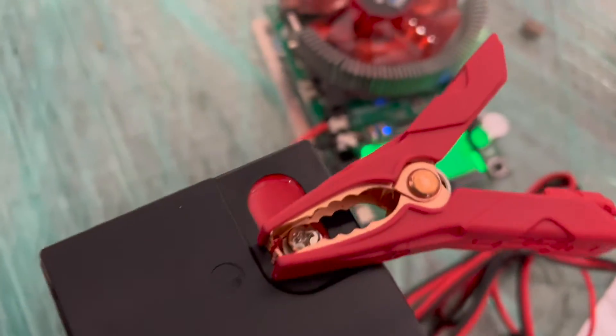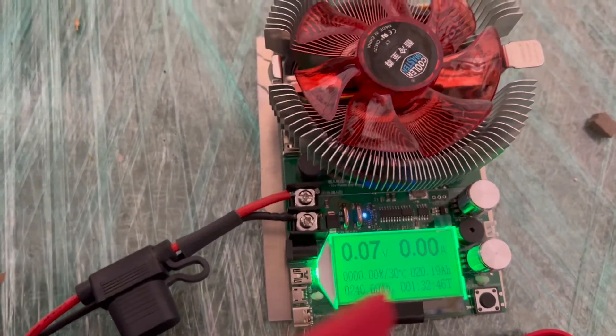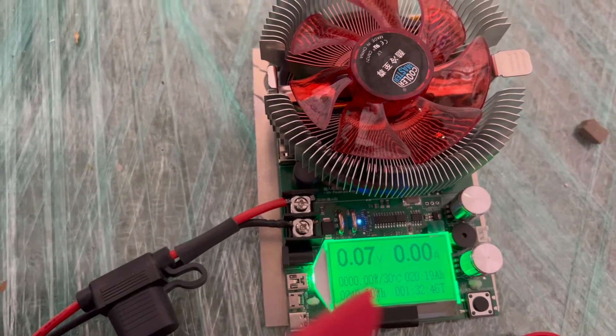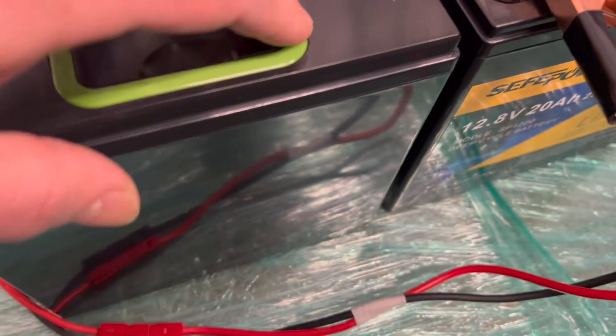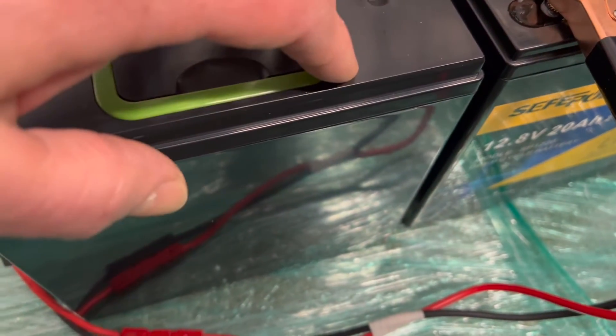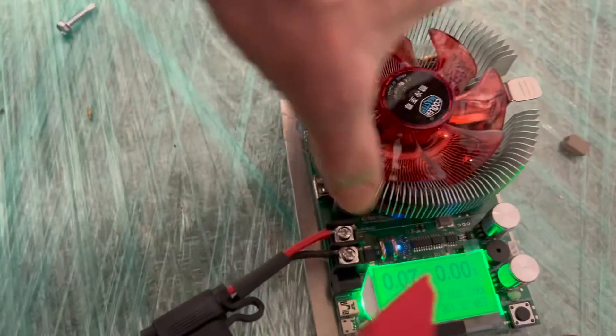So either this is just a one-off issue, or they have a quality control issue with this battery packager. The moral of the story is if you are seriously looking at buying and installing or using any lithium iron phosphate batteries, it's wise to invest in a load tester. Otherwise, we are just running on faith with the stated capacity of these batteries. Load testing before putting the battery in operation is good so you know if you got a good battery off the factory floor, or if you got a lemon and need to send it back.